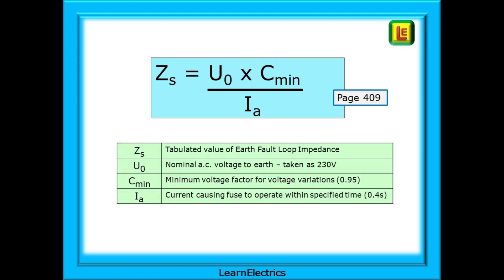On page 409 we find this equation. It's actually very easy to use and what the symbols mean is all explained on the same page. We want to know ZS, the tabulated value of earth fault loop impedance. To do that we will need to know U0, the nominal AC voltage to earth, which is taken as 230 volts for most UK installations. Cmin is the minimum voltage factor, an adjustment that the regulations want us to make to allow for voltage variations. And this is given as 0.95. And Ia is the information that we've just found in the response chart, the current and time data for the fuse in question. So, we're now ready to go.